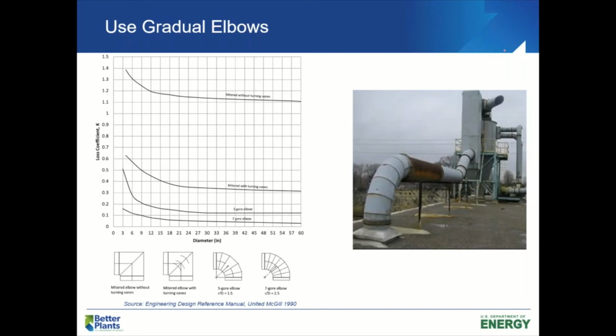And to be fair, this is still very much true in our pump systems, okay? But ideally, we want to use long and slow sloping bends if possible. And why, you ask? Well, it's because of that pressure drop across that turn, okay? And here's an example where, on the bottom left-hand side, this is maybe a super common approach, right? It's just a 90-degree elbow in our system. They're everywhere, all the time, of course. But there's slightly better versions that we can use where it doesn't cause as much of a pressure drop, okay?